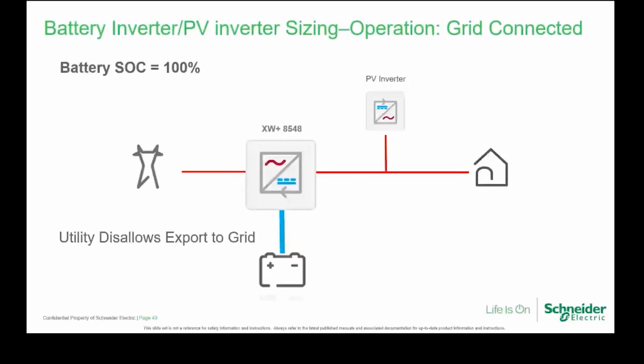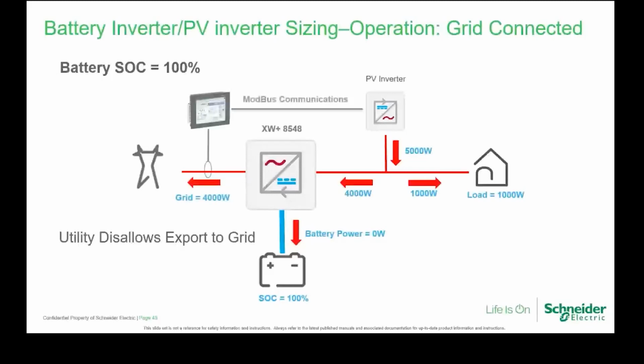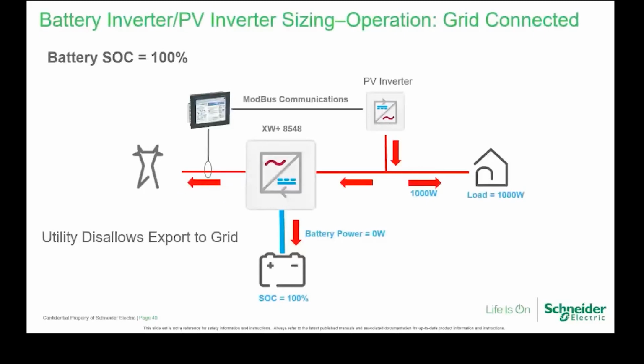So we still have batteries fully charged, loads of 1,000 watts. I've still got 5,000 watts from the PV inverter, and I've still got an excess of 4,000 watts. That will try to push out to the grid because nothing wants to go back to the battery bank. However, you're not allowed to export. So what you need to do is put in a power meter and a PLC. They can communicate, for example by Modbus, back to the PV inverter so that the net flow will be limited to zero by ramping down the PV inverter using the external export limiting device. The PV inverter then only pumps out 1,000 watts, and the 1,000 watts would just go straight to the load and nothing into the XW Plus or the grid.